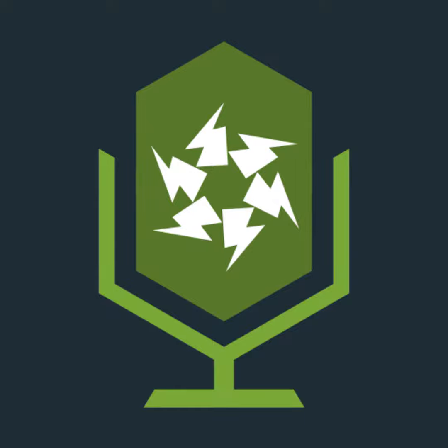Okay, the rest are fairly fine, no sharp edges. Means of fixing, so yeah, it's fine. Alright, 522.9, presence of flora or fauna. Oh, sorry, flora, which is mold or mold growth, is AK. This is plant life. I've experienced this working in a garden nursery once, where a load of ivy crawled into the trunking and it started to twist all around the cables and get everywhere. So plant life has to be trimmed back and kept under control.